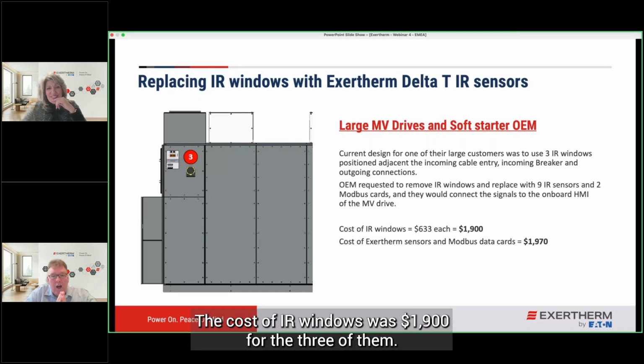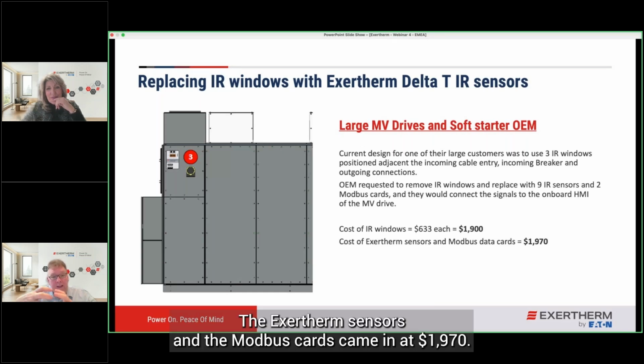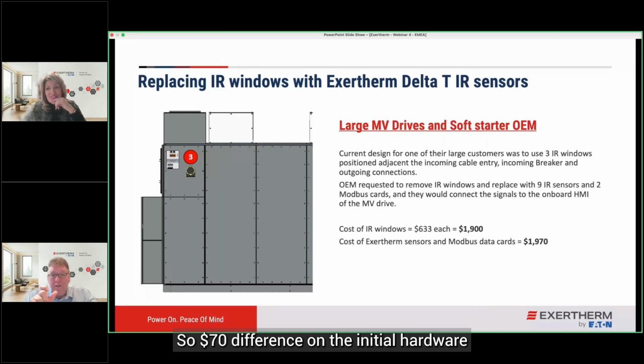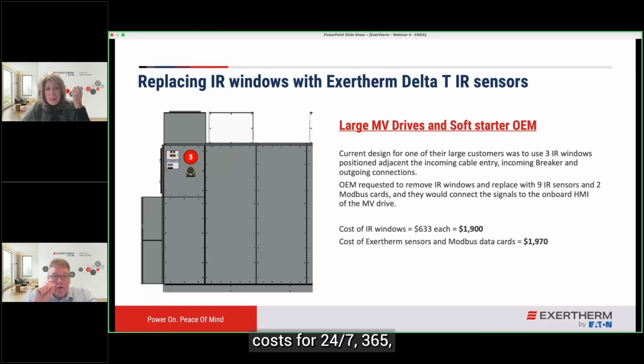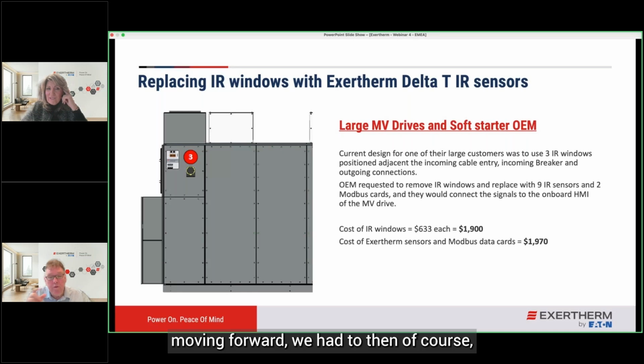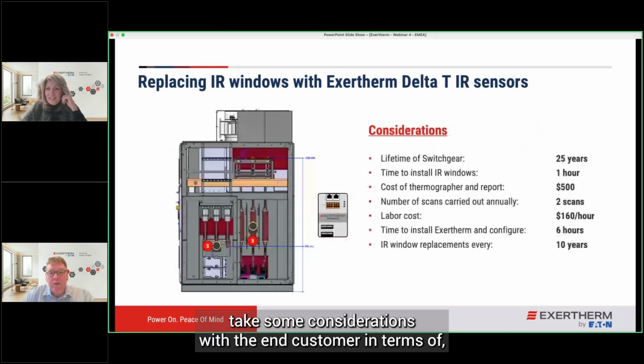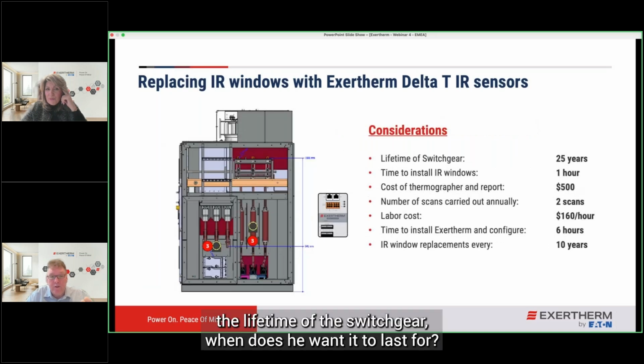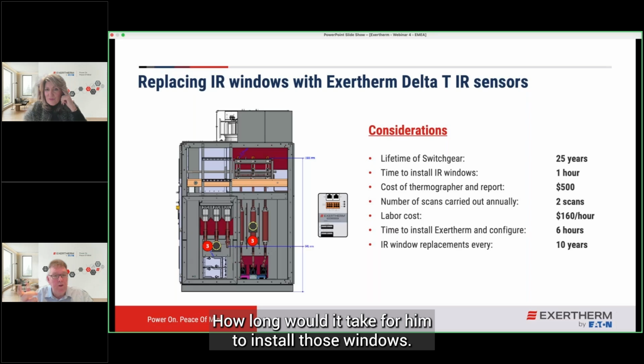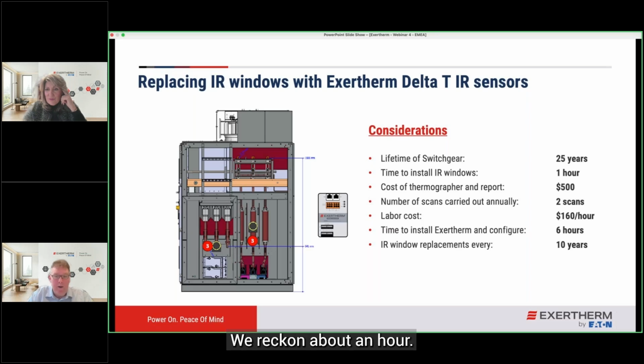The cost of the IR windows was $1,900 for the 3 of them. The Exertherm sensors and the Modbus cards came in at $1,970. So a $70 difference on the initial hardware costs for 24/7, 365 data coming back. Moving forward, we then had to take some considerations with the end customer in terms of how long the lifetime of the switchgear is, and what he wants it to last for. How long would it take him to install those windows? We reckon about an hour.